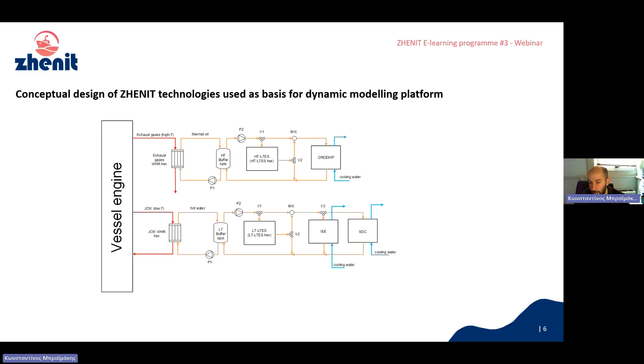So in all of these cases, we have this generic concept in which we have the waste heat stream, be it exhaust gases or jacket cooling water. We have a waste heat recovery heat exchanger, and then we enter the heat transfer loop. In this case, we have the heat transfer fluid, we have a circulating pump, and then we have the buffer tank. This is a pressurized tank that acts as a buffer, basically. Its role is not to do thermal energy storage, but more to stabilize the system. And then we have the thermal energy storage, the latent thermal energy storage. We have a circulating pump, and then we have valves V1 and V2. And basically the role of these valves is to regulate the operation of the system and switch between different operating modes. And I will come back to this point later.